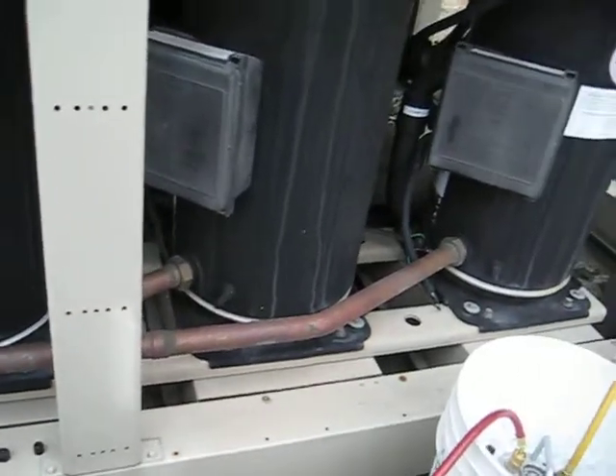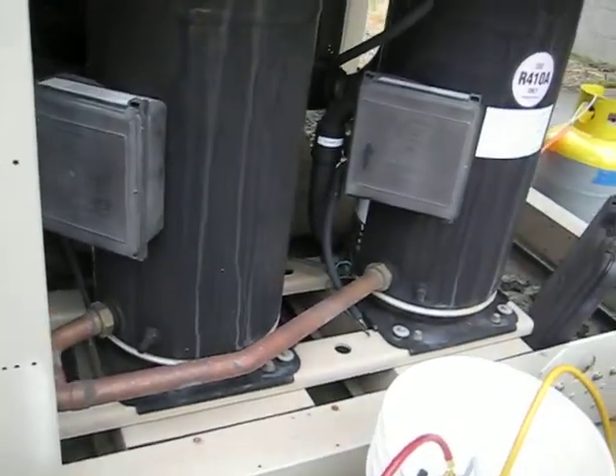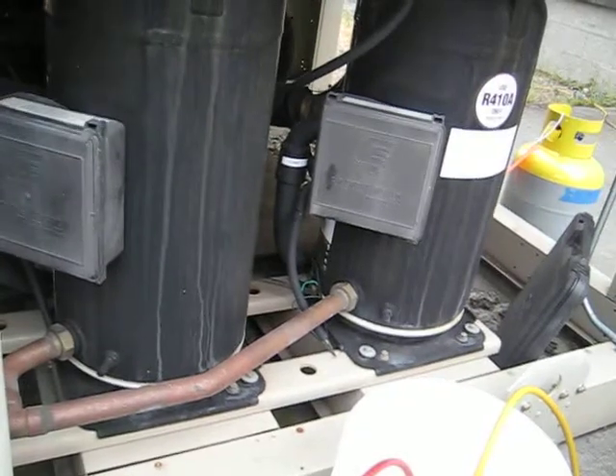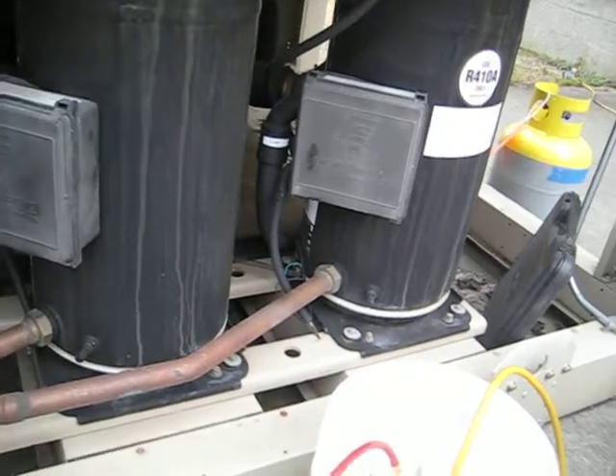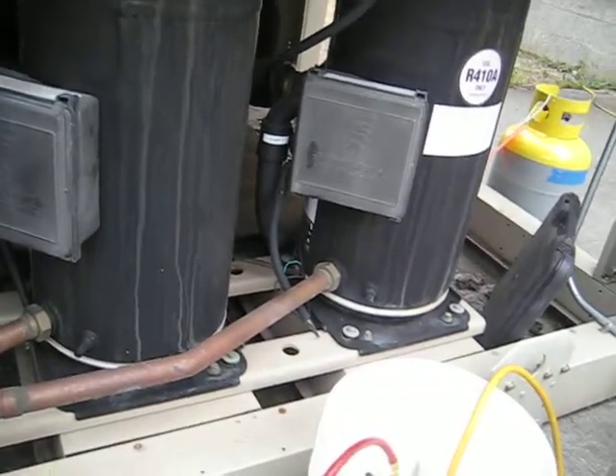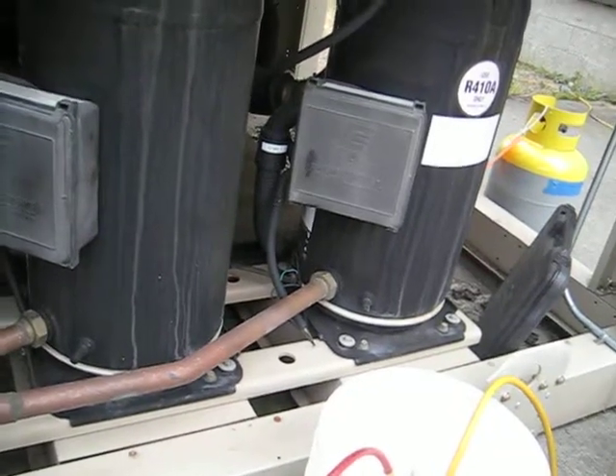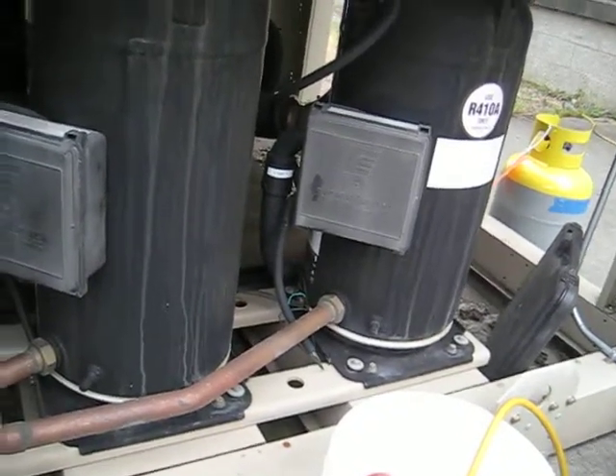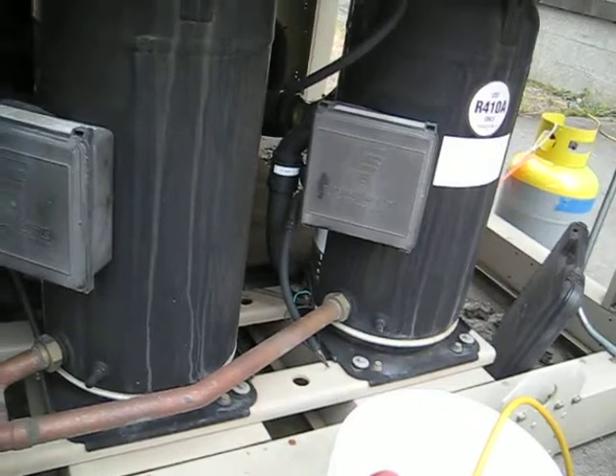So you never want to leave that system open. Whatever you do, if you just put the new compressor in, do it fast. The compressor will come nitrogen charged with a few pounds of nitrogen, say 20 or whatever it is. When you pull the rubber plugs out, it goes shh. If you don't hear that, I'd be worried, because air could have got inside the compressor and contaminated the oil.